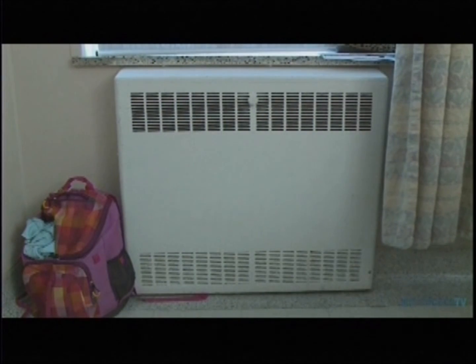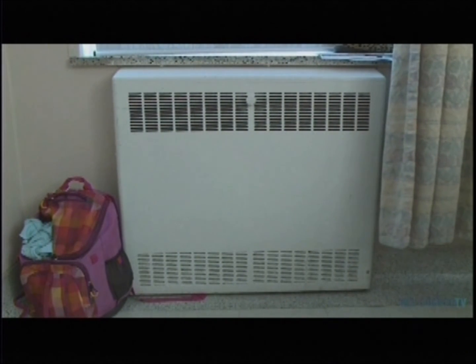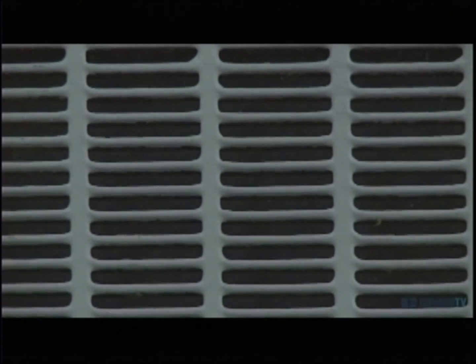Way back on the back wall, you see the heating elements. They've got fins on them. Not ideal from an infection control perspective. We wouldn't do that today. Ventilation standards, again, they're subpar based on what we would do based on ASHRAE standards today.